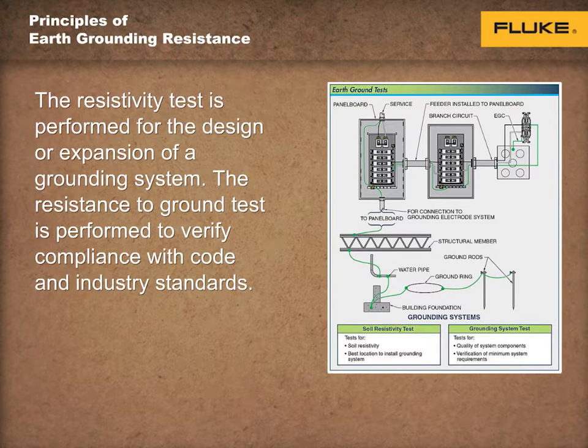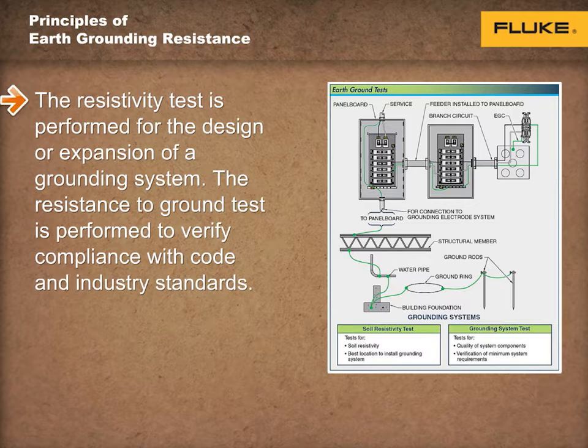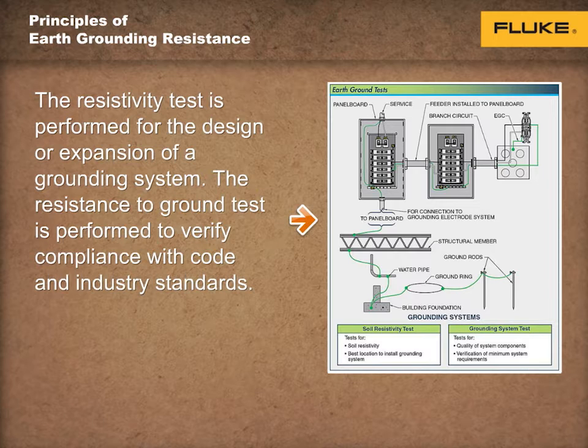There are various types of tests that can be performed to obtain the resistance to ground value. The most common test methods are the Wenner and the Schlumberger methods. With these methods, the ground resistance is measured and a formula is applied to determine the resistivity value in ohm-meters, which is performed to determine the condition of the soil in which the ground electrodes are to be installed and the best grounding method to use. This is done on new building construction sites and other structures that can carry electrical system fault currents or lightning currents, such as cellular telephone towers and utility substations, as part of the initial design and specifications.